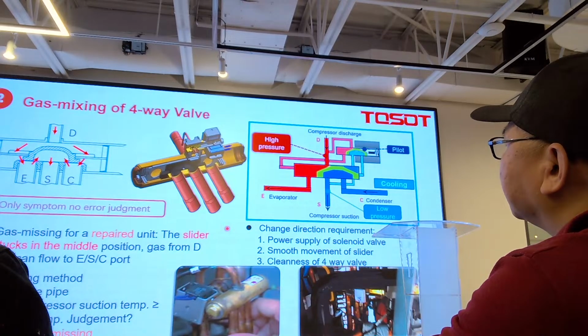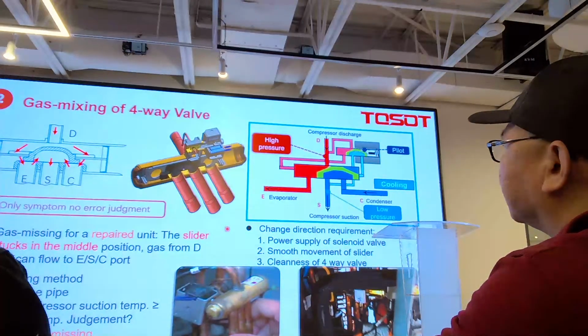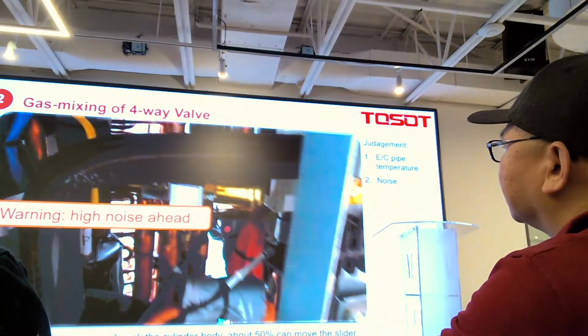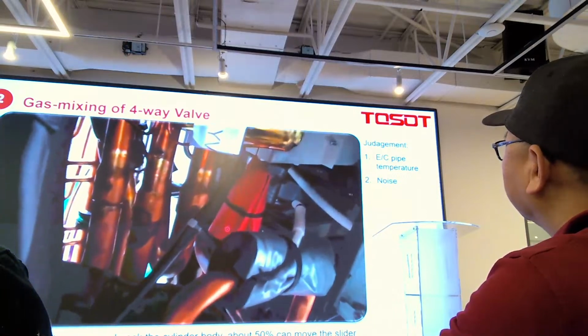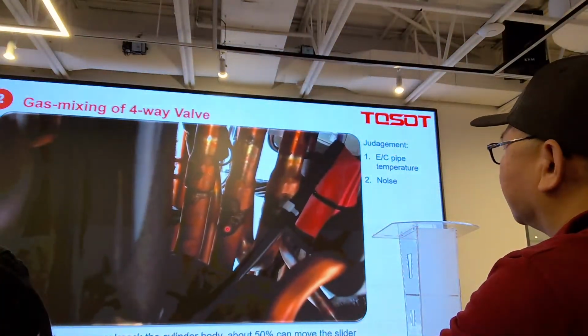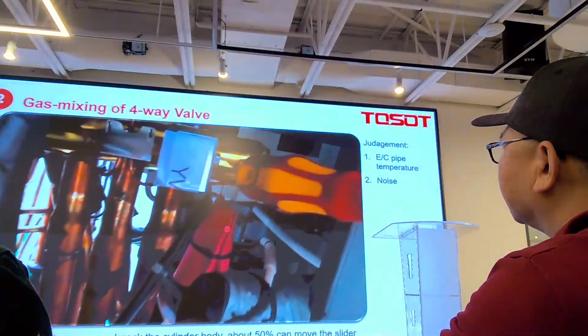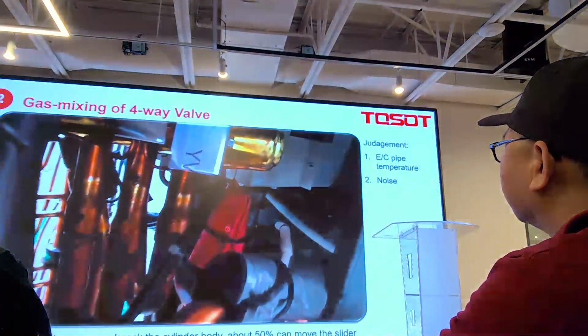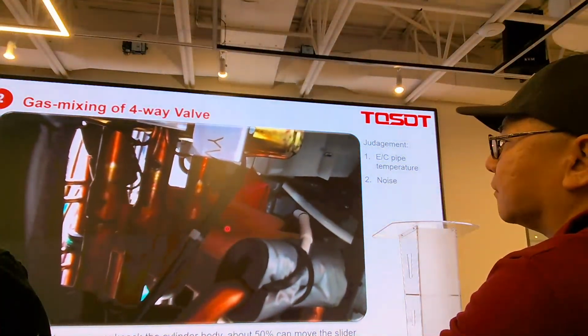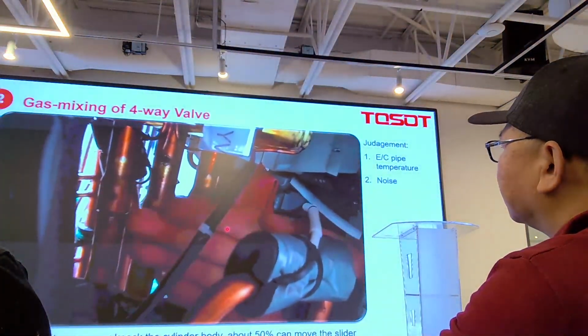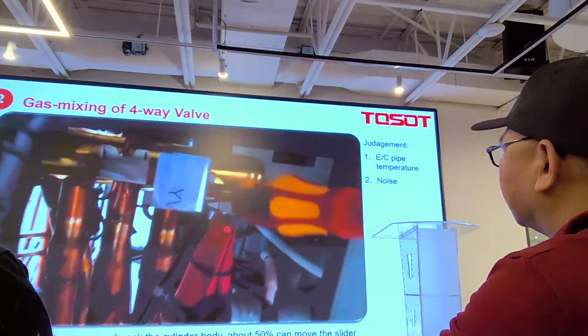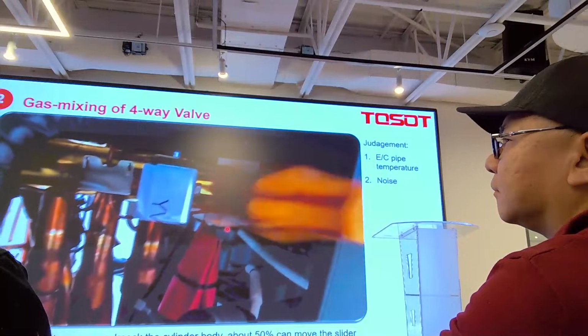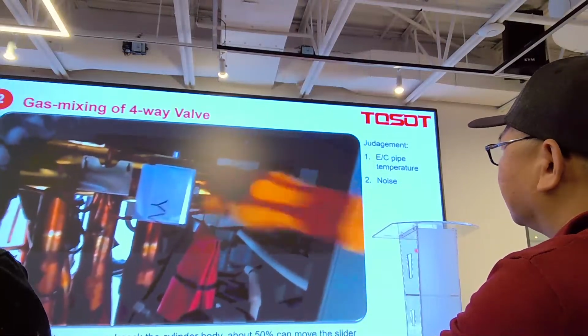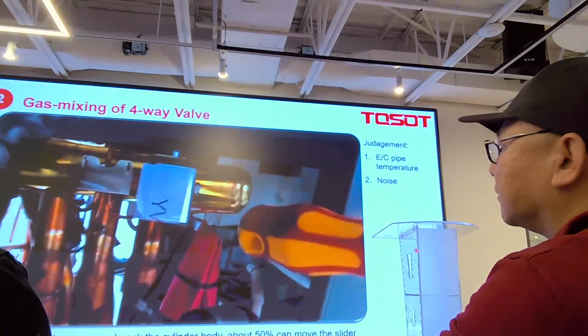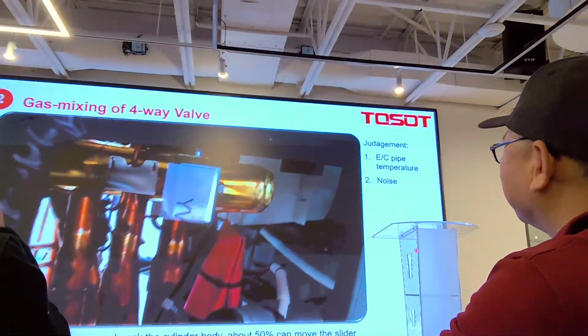And later I will show you videos how we fix this one temporarily, which is this. First, you can find that the compressor noise is huge. And then our service person also checked the two pipes to feel the temperature, which is almost the same. This we already know it is malfunction, so we just use the screwdriver to knock the four-way valve body. You can see already fixed. This is only for temporary.